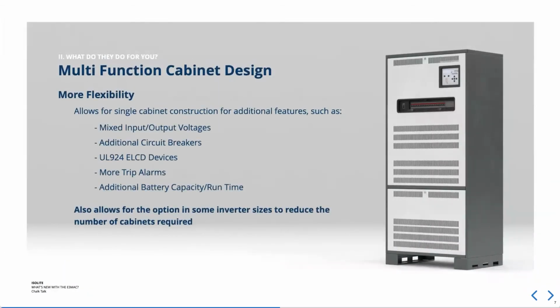The multifunction cabinet has a lot of arms and legs for us. One thing we've had trouble furnishing in the past is mixed input and output voltages, or more particularly mixed output voltages, like 120 volts in but needing 120 and 277 on the output. Historically that's involved an additional enclosure, which isn't great because it takes up a lot of floor space for something that doesn't deserve that much value. This new design lets us do things like that, among others.